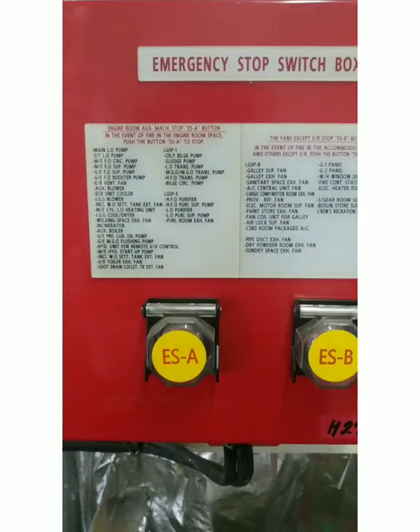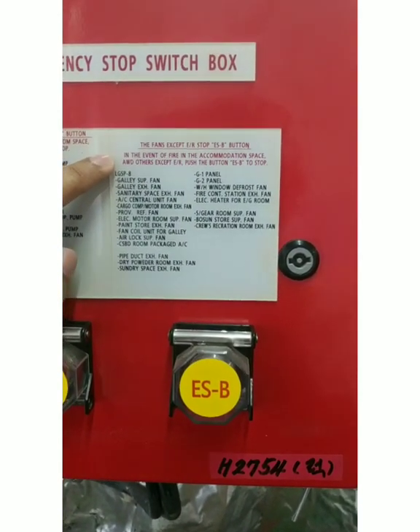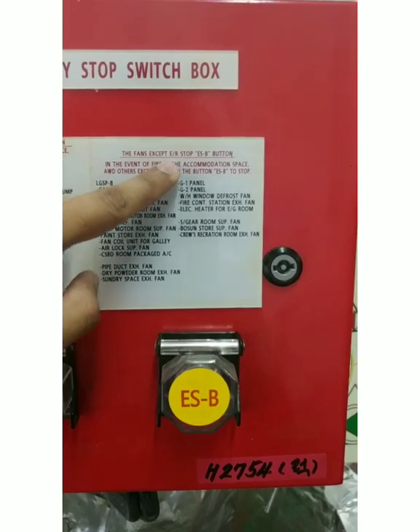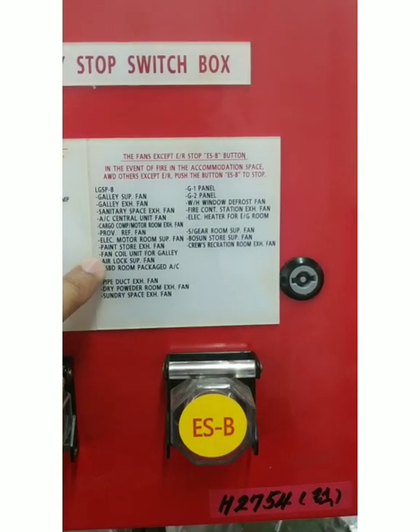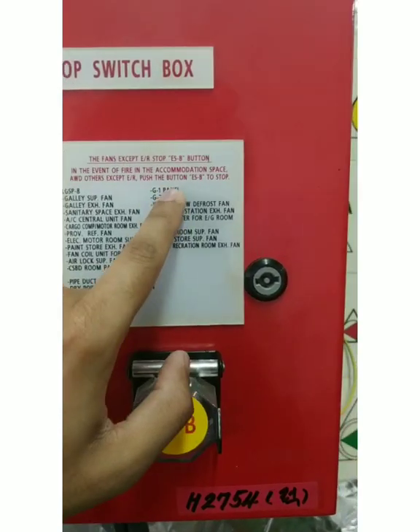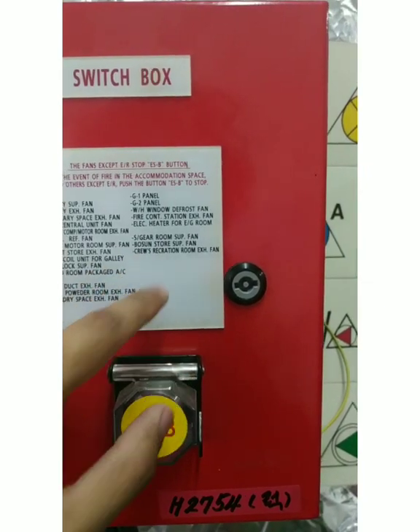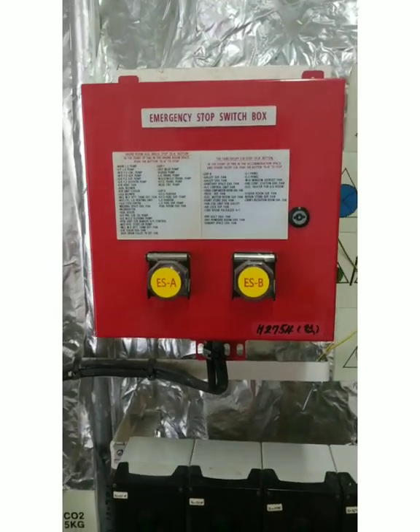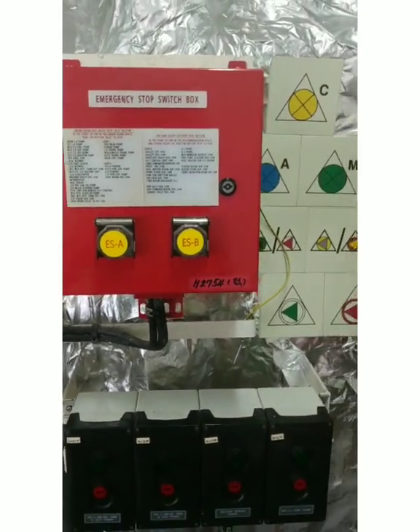ESA has to be activated when there is a fire in the engine room. ESB is for the deck or accommodation: 'Fans except engine room — stop ESB button.' So only accommodation space fans will stop; the engine room fans will not stop. The areas covered include galley supply, sanitary space, cargo comp/motor room, pipe duct exhaust fan, DCP rooms, dry space, G1 and G2 panel, galley, s/gear room supply fan, and boson store. If there is a fire in accommodation, press ESB to prevent smoke from spreading inside.